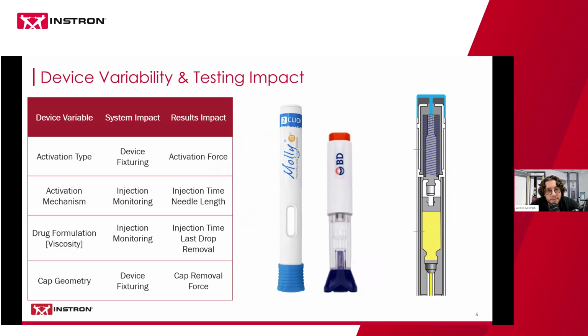So there's also a good amount, and this is to more specifically work through what different types of variability there is and what kind of impact that has on the test system and on your results. The most basic one is, in the world of auto injectors, there's typically two main activation types. You have needle shield or two step, and button activated or three step. The difference between those two will have a big impact on making sure my system can activate the device, and the mechanisms to do that are extremely different. And your force profile will also look extremely different depending on which type of activation mechanism you have. So that's just one variable.